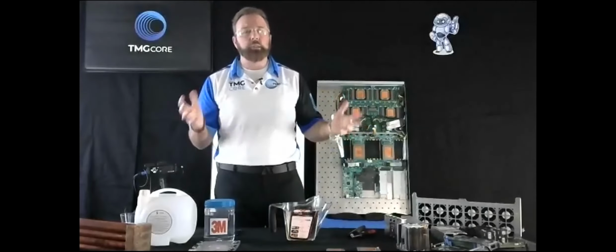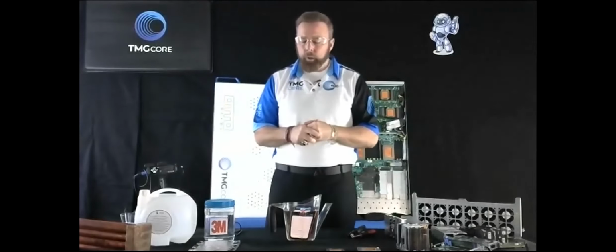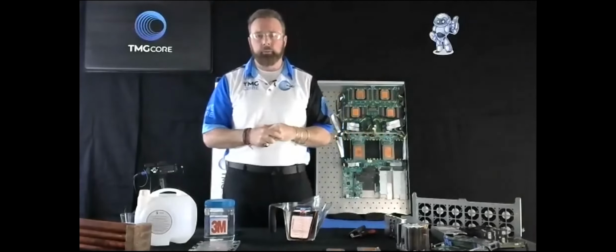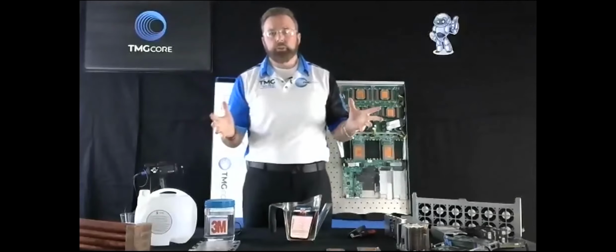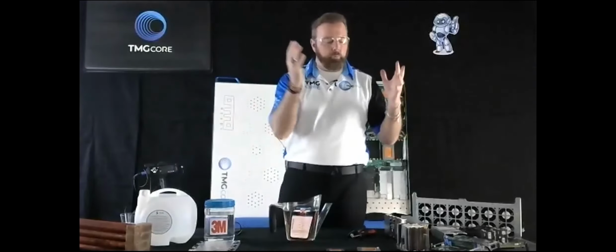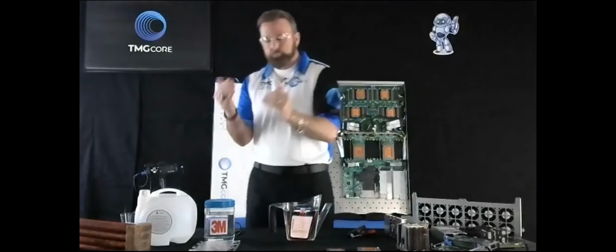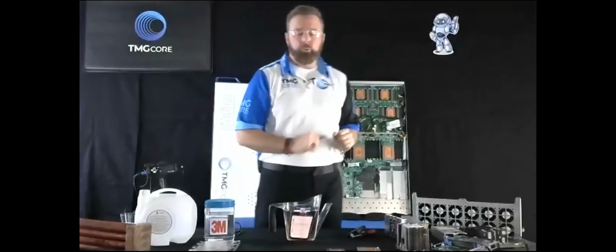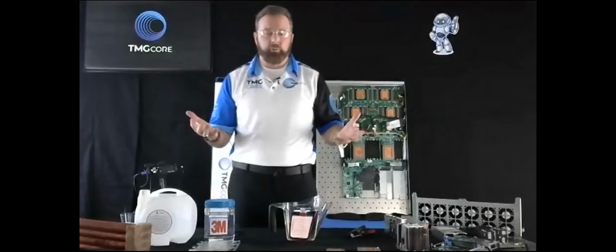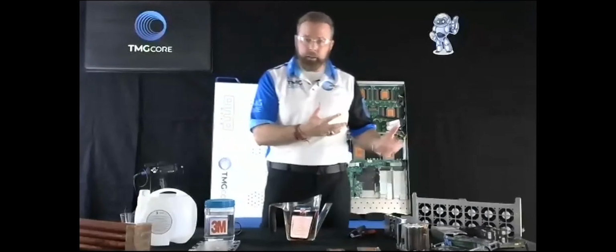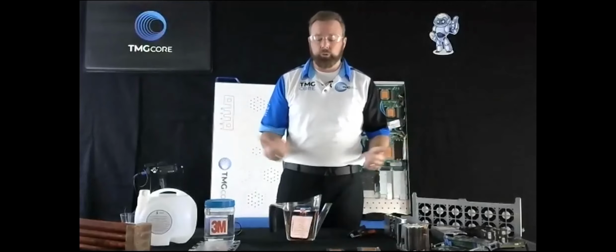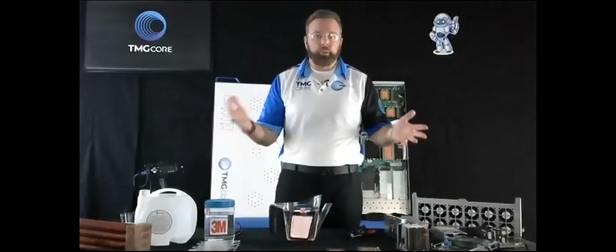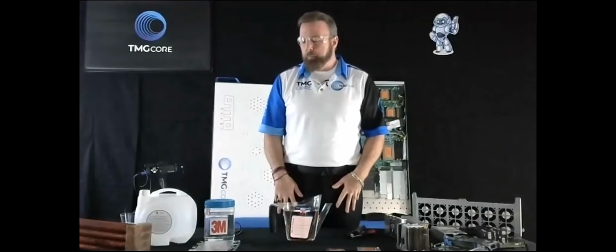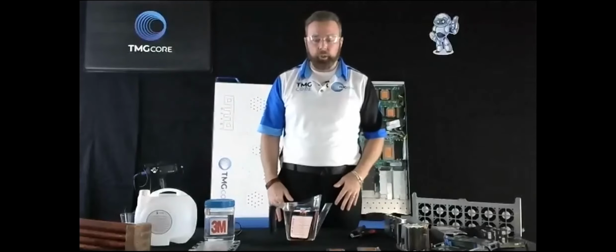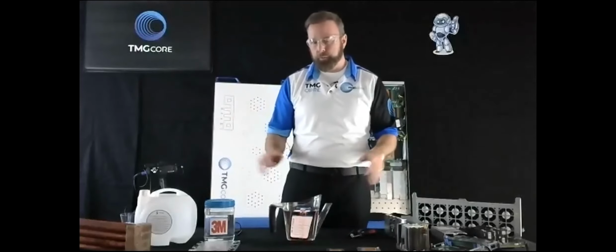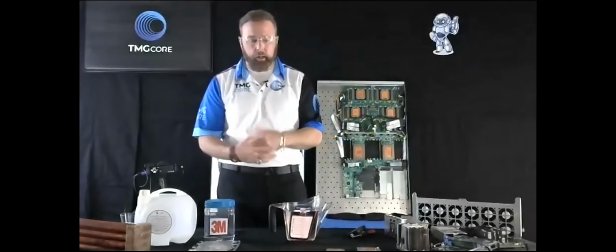All our systems are fully redundant as well, using what we call fault tolerant design methods, so that all the systems can be operating. You could have one pump fail or a power system fail, and the system still maintains itself and still operates, and it can be maintained while it's operating, so you don't have to shut it down. For N+1, N+2, N+3 configurations, military applications and so on, two-phase immersion cooling through the Otto platform is phenomenal because you have that security backup.